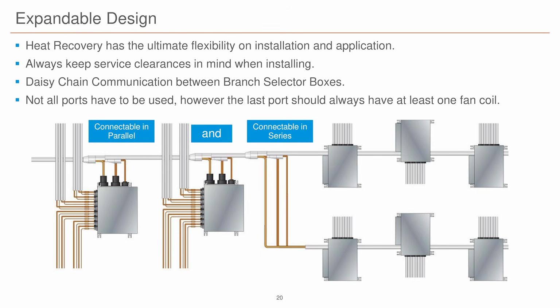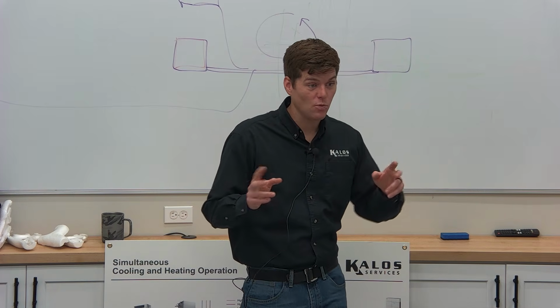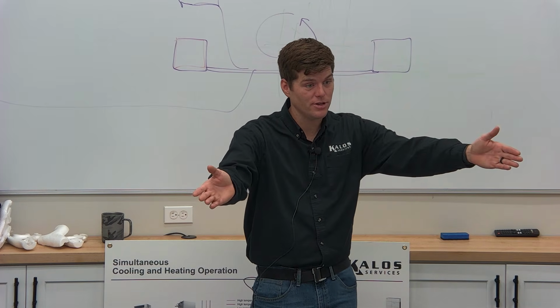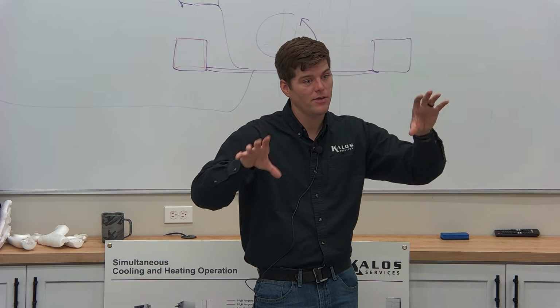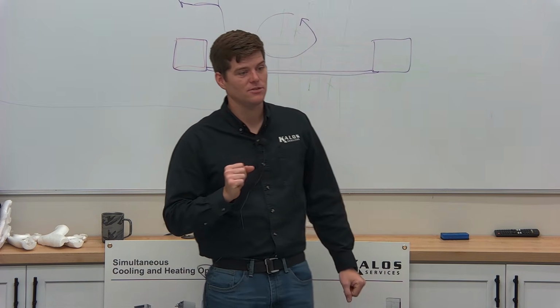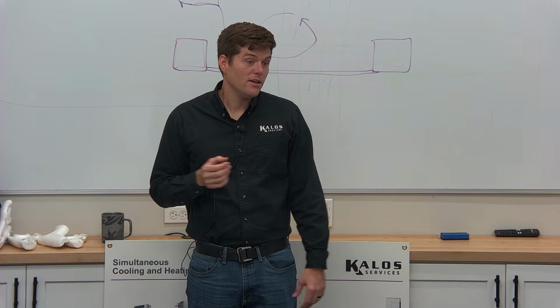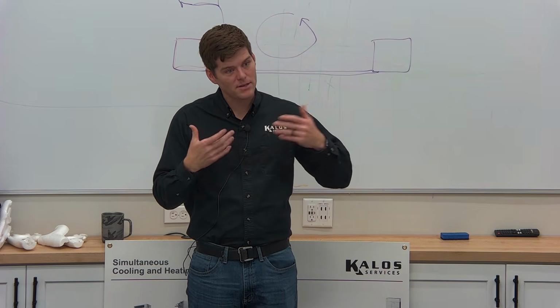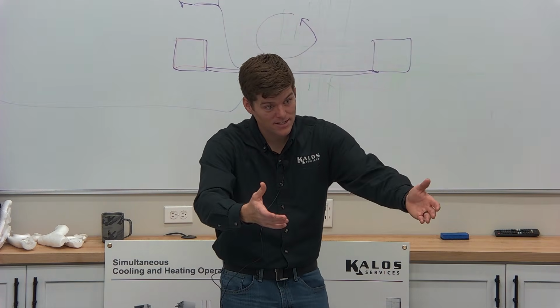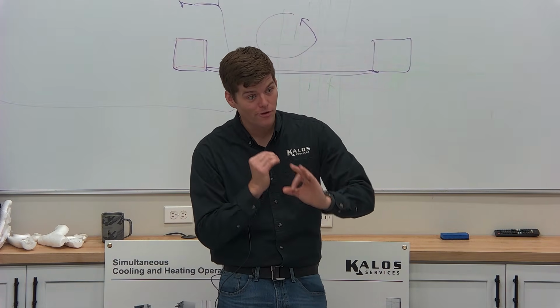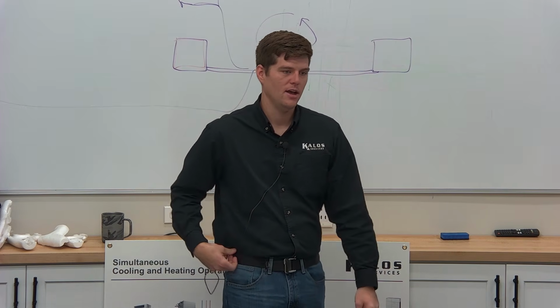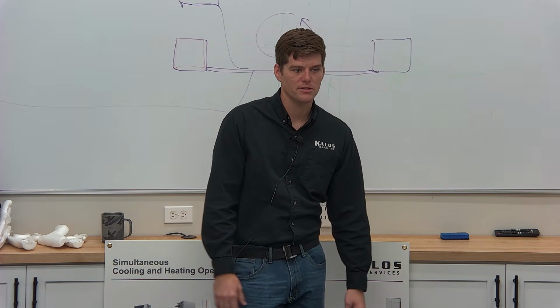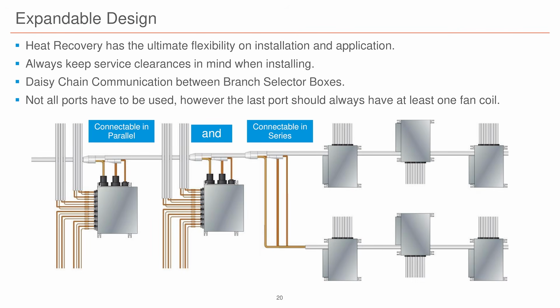Yeah, because you can also take these boxes here and instead of connecting 18 indoor units on 18 ports, I could probably connect up to 24. Because I could take the one line off and I could branch it to 2 indoor units and they're both tied to that one port. So they both have to do the same thing at the same time, but I can still deliver that same capacity. It's just flexibility. And all of that also comes down to refrigerant piping size, being able to give that capacity to get that flow through there and the volume that you need to those units. And there's not a whole lot of restrictions in these boxes, the way that they're set up. But that's the thing, right? That's the premise behind this.